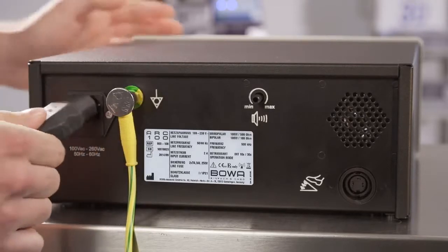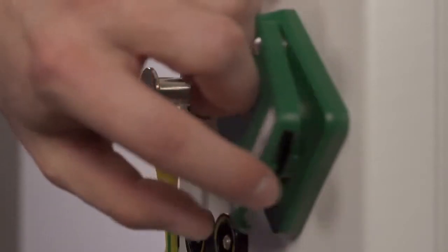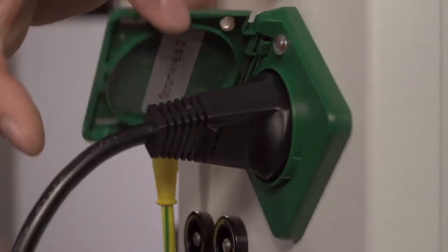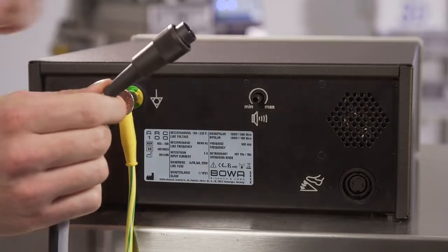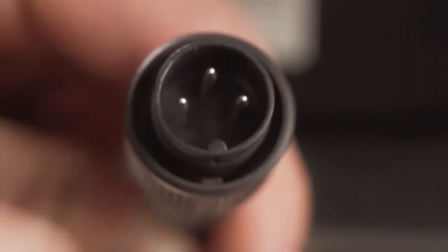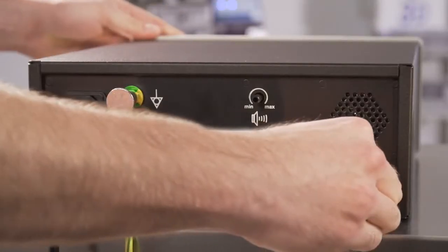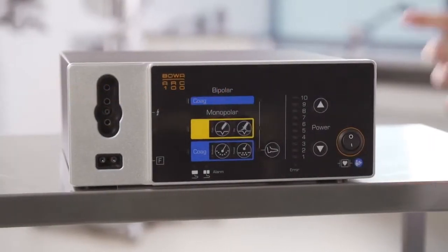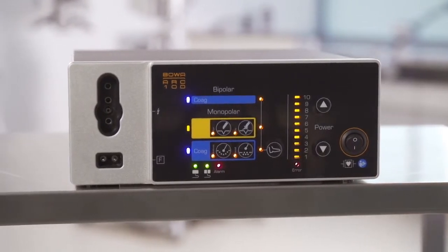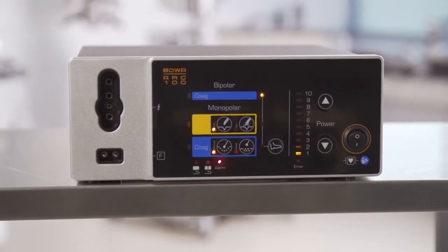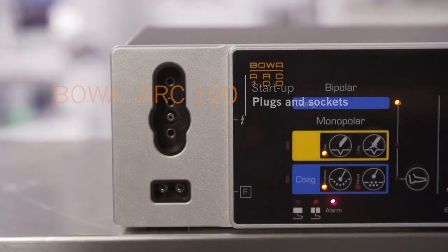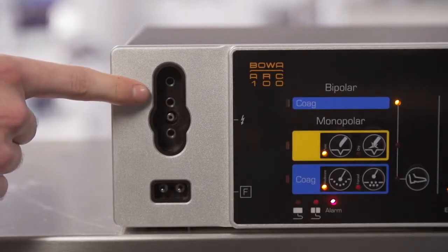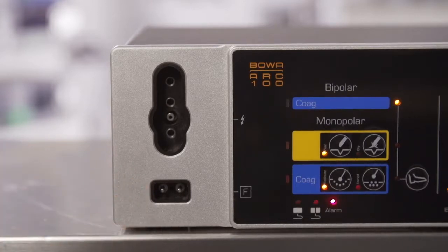Now plug the mains cable into the supply connection for inlet connections of kettle plug socket and connect it to the power supply. Next, connect the cable from the foot switch to the ARC 100, making sure that the little lug on the foot switch plug is correctly positioned in the socket. Switch on the ARC 100 generator using the on-off switch. The ARC 100 has a mono-bipolar multifunctional socket and a socket for the neutral electrode for monopolar applications. You can connect 3-pin plugs, standard 4mm plugs and the bipolar BOWA ARC 100 cable here.